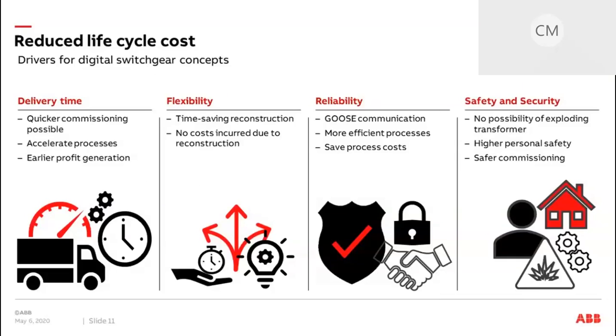A digital switchgear can be delivered faster. The faster delivery time is due to the time-consuming CT data clarification being deleted from the ordering process, because one sensor size fits all. What we do in digital switchgear is we use sensors with a linear curve which do not go into saturation, so basically Rogowski coils instead of conventional current and voltage transformers, in combination with a modern relay with IEC 61850 communication and maybe some optional monitoring and diagnostic features.